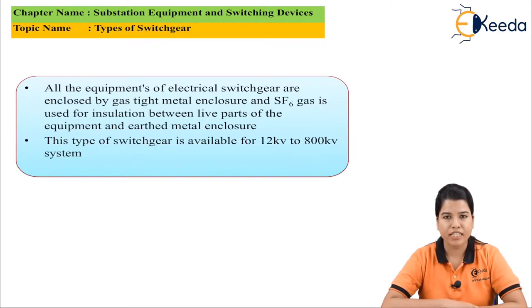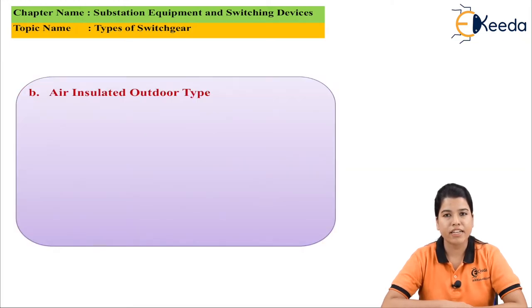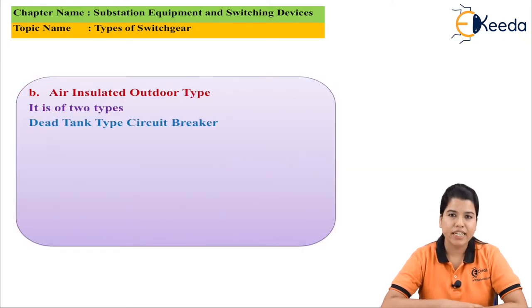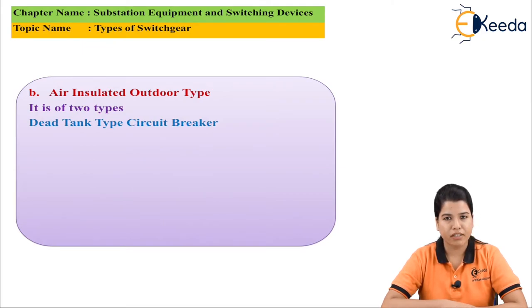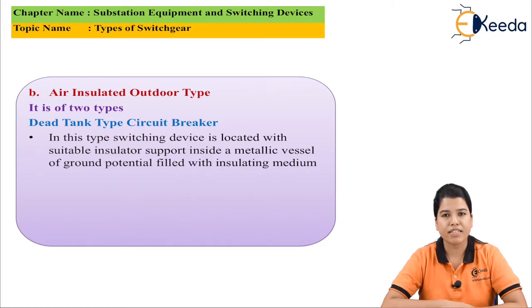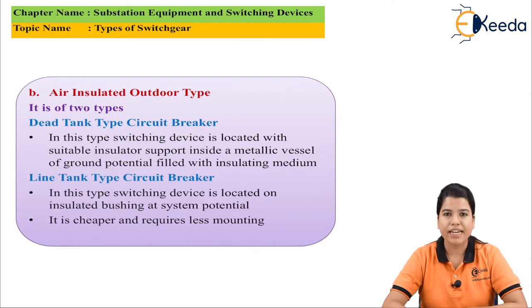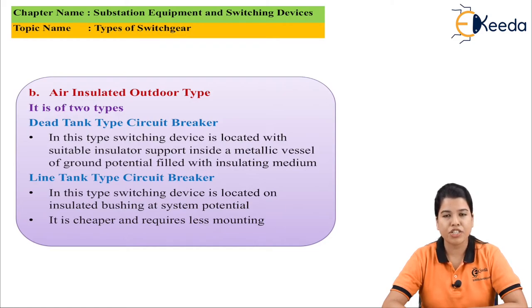This type of switchgear is available from 12 kV to 800 kV. The air insulated outdoor type is again of two types. First is the dead tank type circuit breaker, where the switching device is placed inside a vessel at ground level with an insulating medium. Second is the live tank type circuit breaker, which is cheaper compared to the dead tank type, and in this the switching device is located at an insulated bushing.